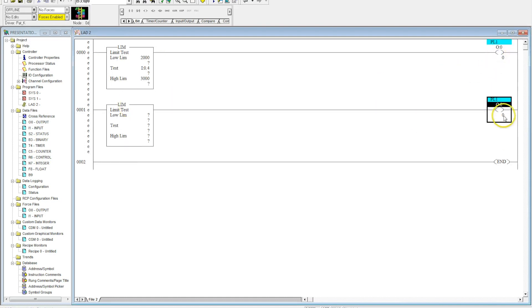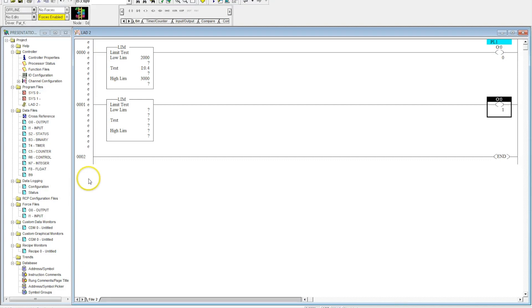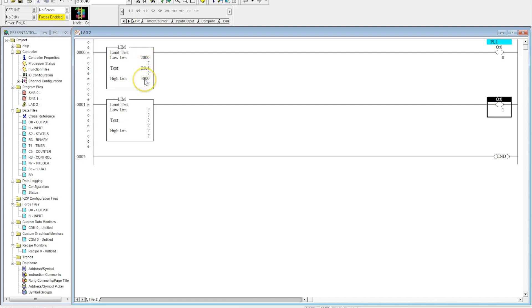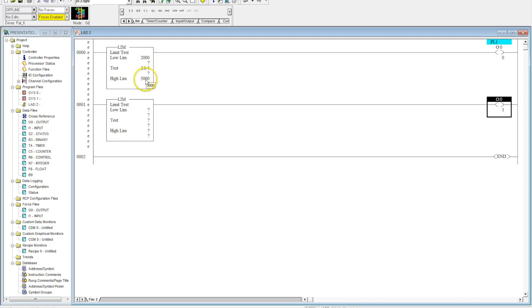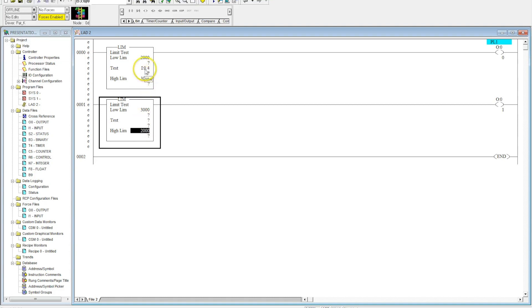The limit test actually works two different ways. When you have the lower number in the low limit and the high number in the high limit, the output will be active or the instruction will be true when the number is between the low and the high. But I can also switch that - if I put the high number in the low limit and the low number in the high limit, it will be false when it is between these numbers.